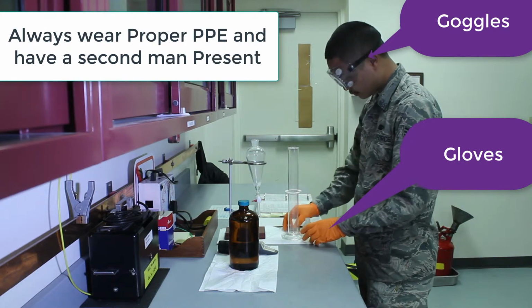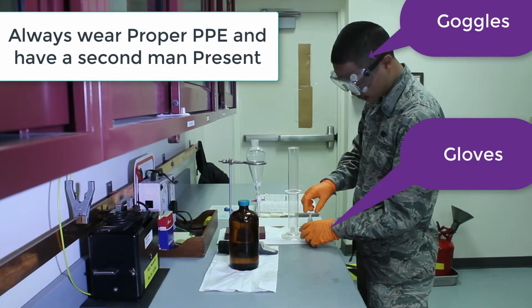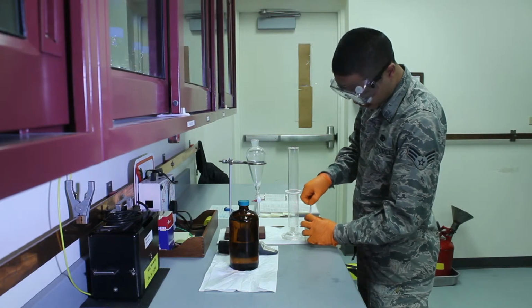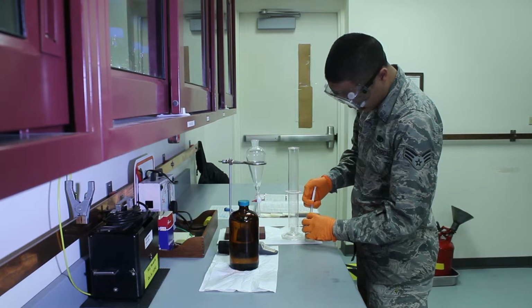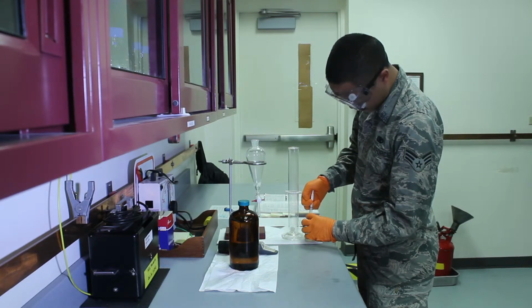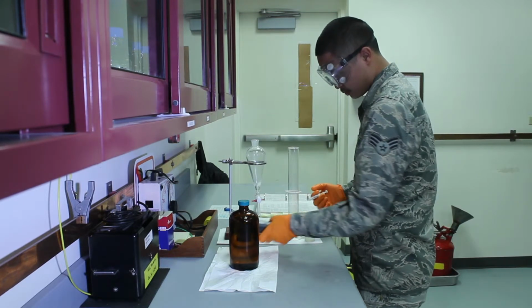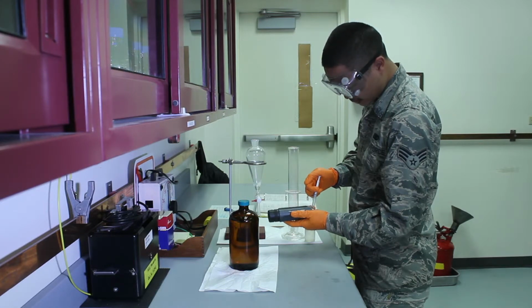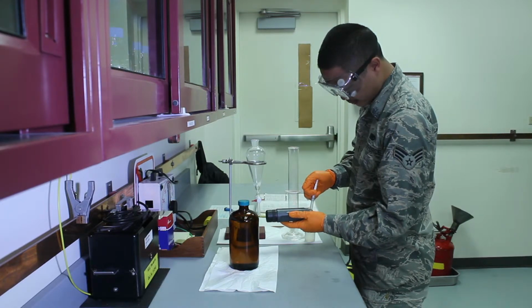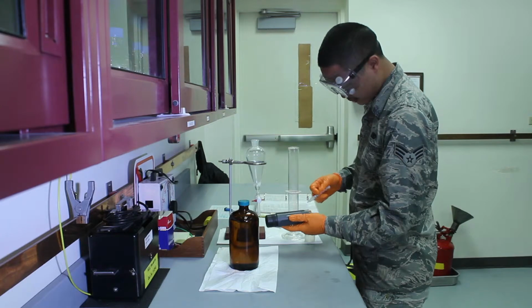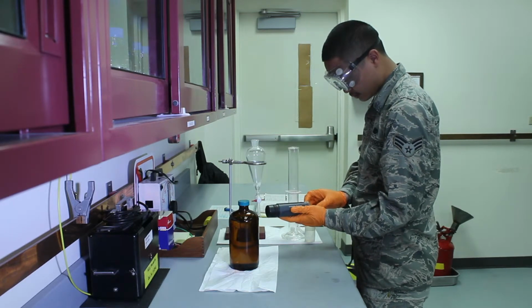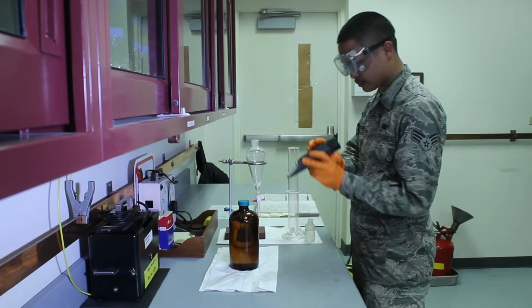Before the test can proceed, you must calibrate the refractometer. Hold the refractometer in a horizontal position, lifting the prism cover plate, and make sure that the prism and cover plate are clean. Using a plastic dipstick or common plastic syringe to prevent scratching the prism, place a few drops of water from the aluminum dish on the face of the prism itself. Close the cover plate and observe the location of the line in the viewer through the eyepiece.